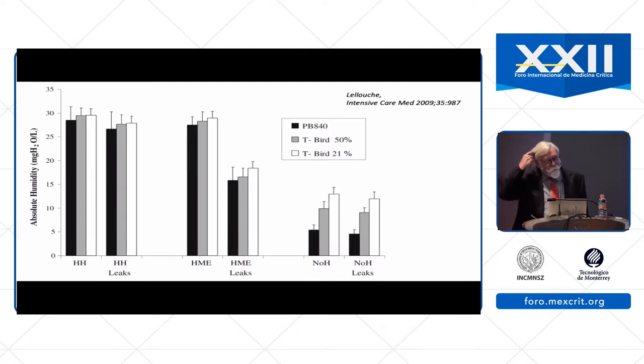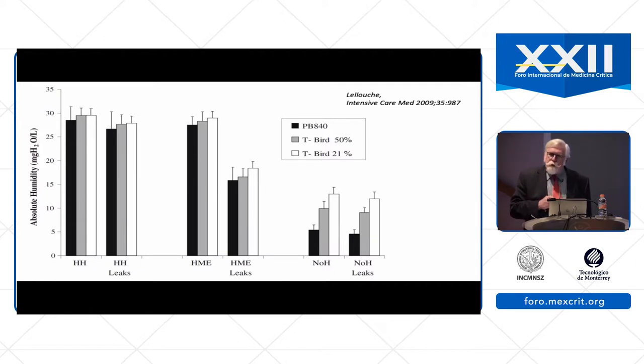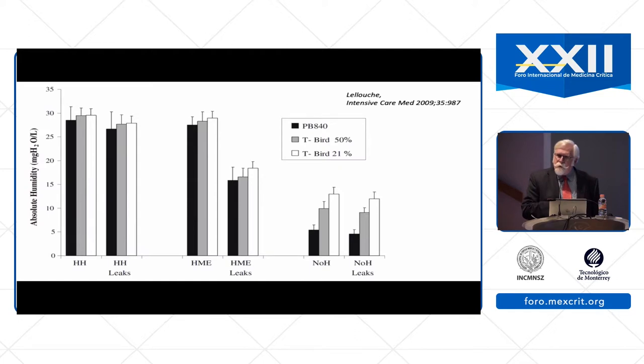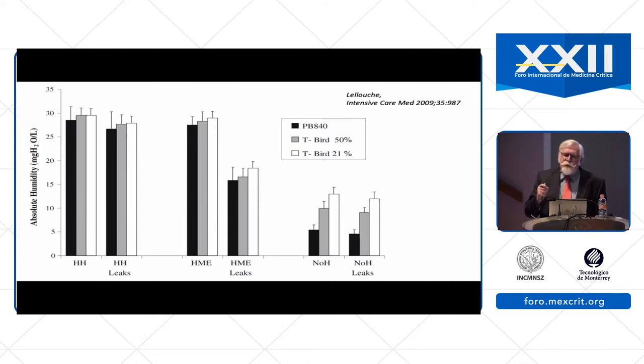This is another study by the same group, published about 10 years ago, looking at the effect of leak during non-invasive ventilation with a heat and moisture exchanger versus a heated humidifier. With the heated humidifier, if there are leaks, the delivered humidity remains relatively constant. However, with the heat and moisture exchanger, if there are leaks, there is a substantial decrease in the amount of humidity delivered. Again, this is because the performance of the heat and moisture exchanger requires that the patient breathe in and out through the device, and if there are leaks in the system, that defeats its performance.